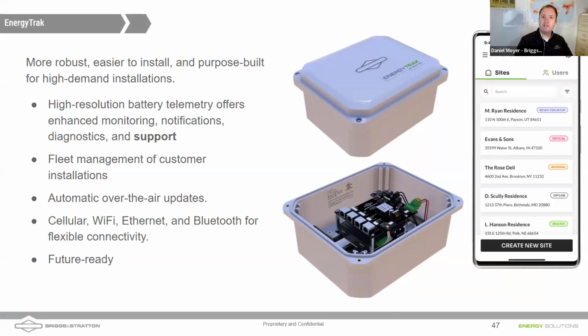One thing this device and app offers is that it communicates more directly with the battery. The battery and the inverter are talking to each other, and the battery is transmitting a lot of parameters to auto-populate set points in the Solark and EG4 inverters. It's battery temperature, to maybe do cold weather curtailment if it gets there. Our battery can go down to 14 degrees ambient, where a lot of our competition's is 32. But when you add this device, it really gives you higher resolution of the battery parameters and also notifications, which can help you with tech support. Our tech support can obviously remote into the MySolark and the EG4, but they can also remote into this device, look at your system and help you quickly troubleshoot any issues that may be happening with the batteries. As an installer, you still get fleet management. The customer still gets access to this.